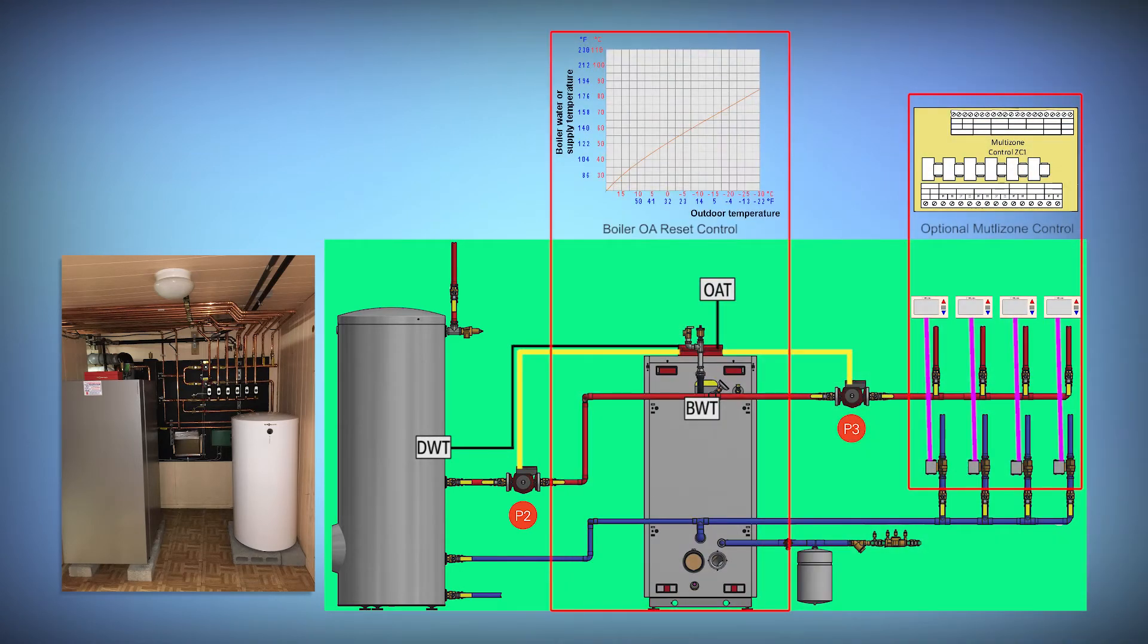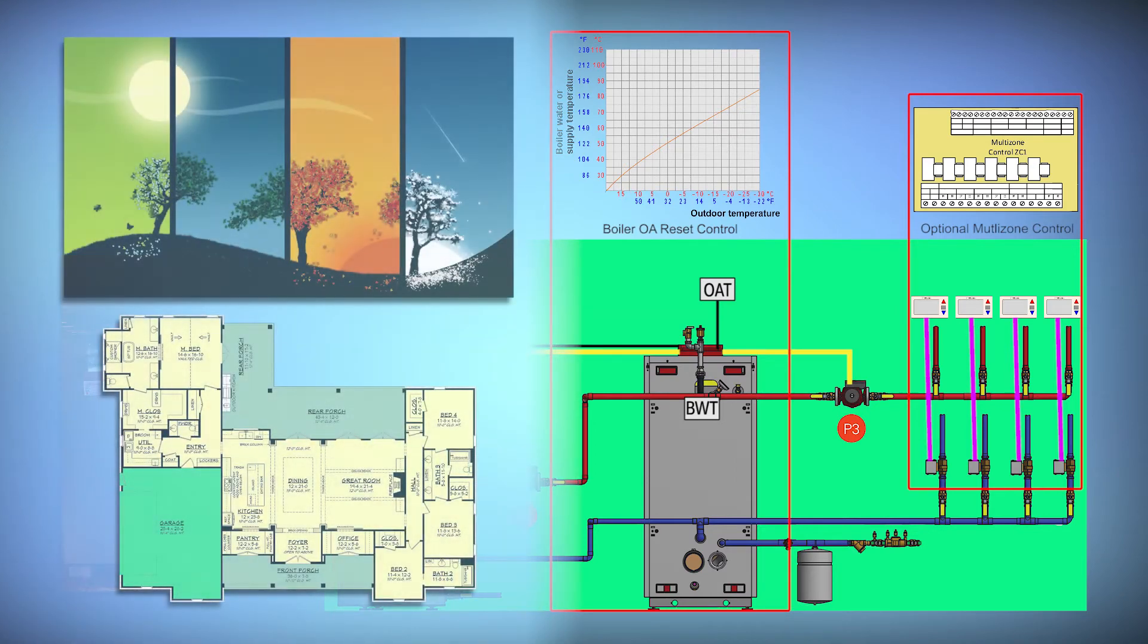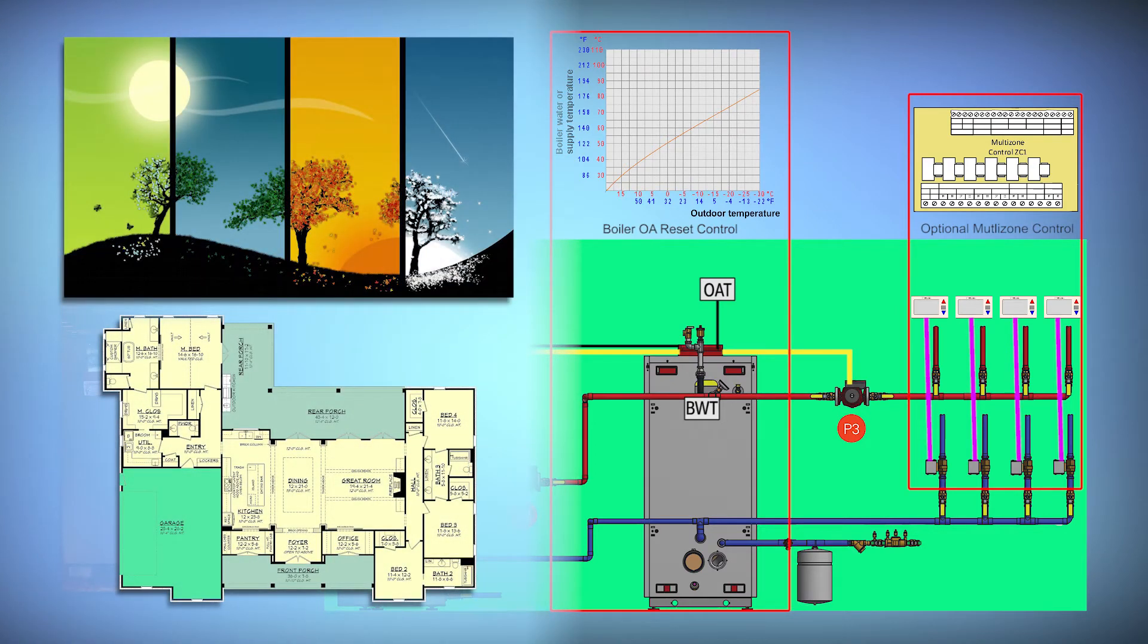Remember the modern boiler has an outdoor reset control so it can adapt its water temperature to the heat loss in the building based on outdoor temperature. It can also adapt to the zones that are opening and closing by seeing the water temperature coming through the boiler or the common supply sensor in a primary secondary system.